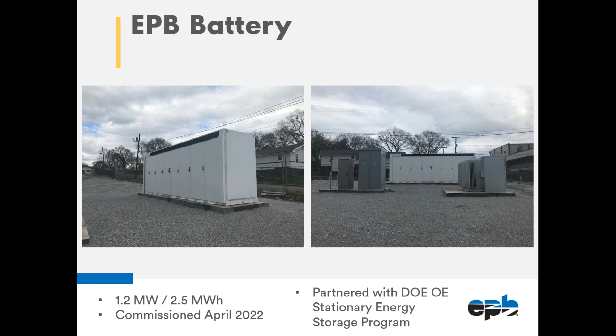Going back to our use cases, for this project specifically, we're able to save a little over $100,000 a year on our demand charge, and the net present value calculations worked out pretty well for us. The microgrid capability I described a little while ago offers about a third or fourth level of redundancy for our control center campus. This was also one of the batteries we were able to use for reducing our demand when TVA had its capacity shortfall event.